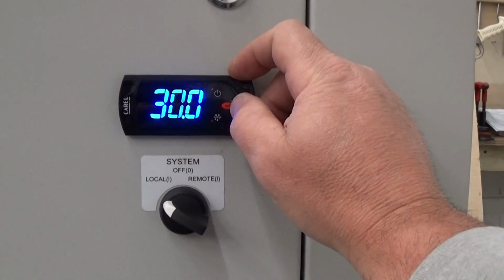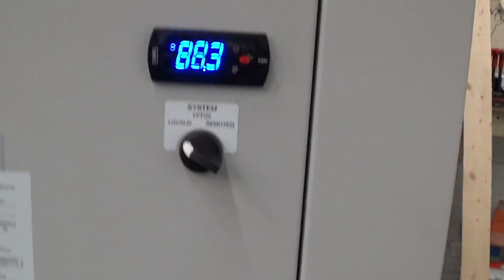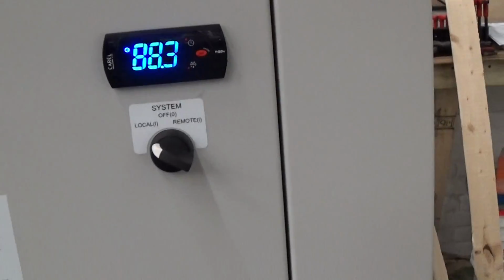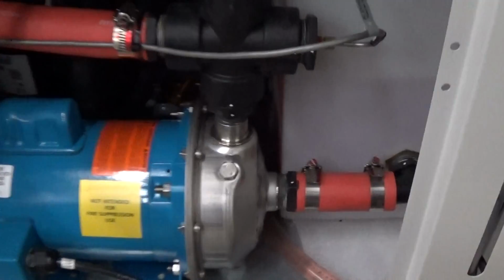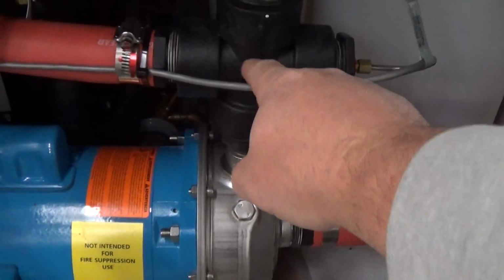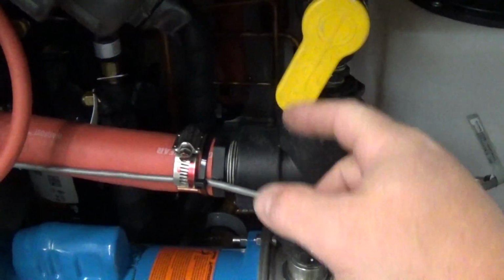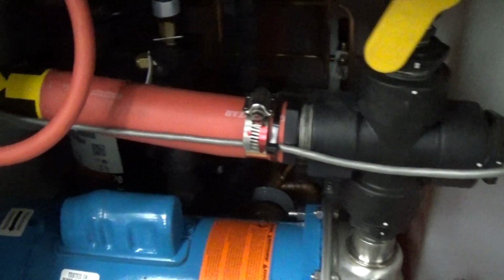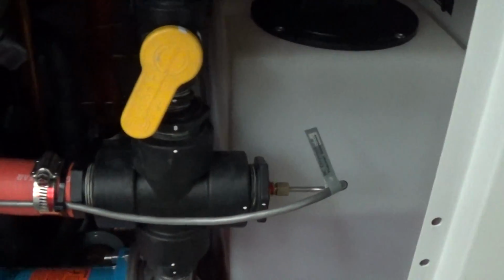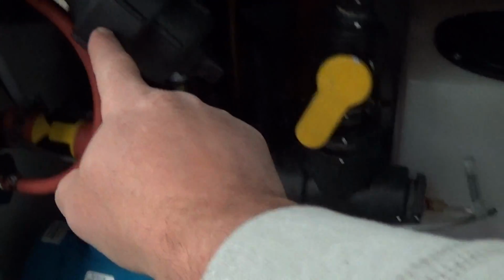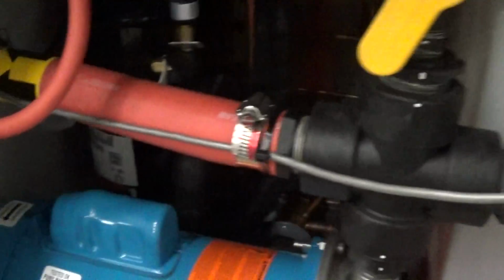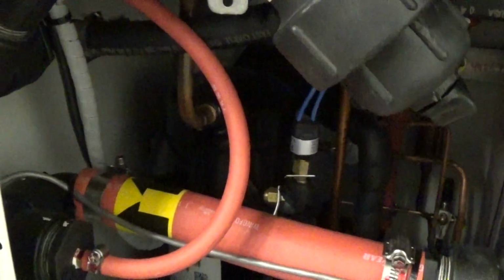I guess I could have just gone that way. Just press set again. And the fan kicked on. Our compressor's going. Now in this unit, the pump draws off the tank, comes up and goes out through here, out to our process. We also have a little bit of a bypass here. That's adjustable, nice. Fluid inlet into the chiller comes in through here. We've got a nice Y strainer, you should clean that often. And that curls back and goes back to the brazed plate exchanger in the back corner. And there's your 2 horsepower compressor right there.